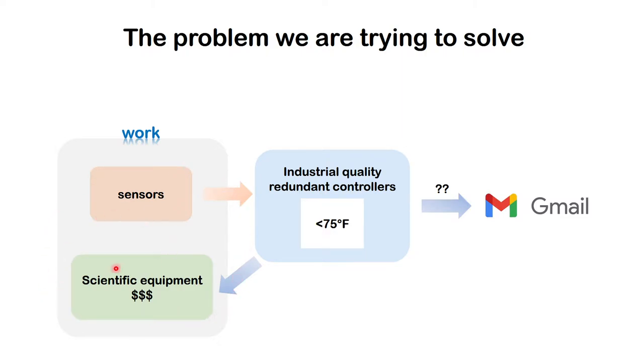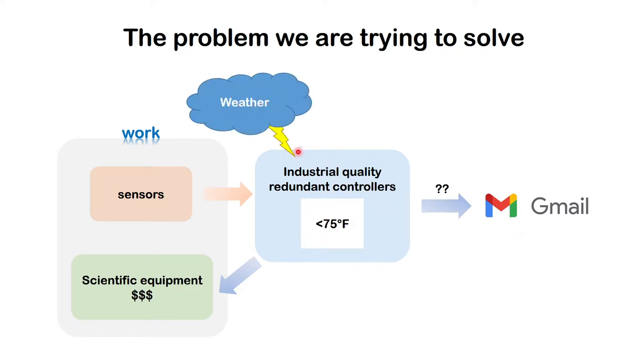Every time I go to this particular room I can check the temperature and give feedback on what needs to be adjusted. Ideally this would send out emails with warnings if something goes wrong, but the problem happens especially during weather events — specifically the transition from winter to summer, when the ACs and heaters don't go on and off at the same time. The temperature controller kind of becomes a hit or miss and we end up with non-ideal room conditions.